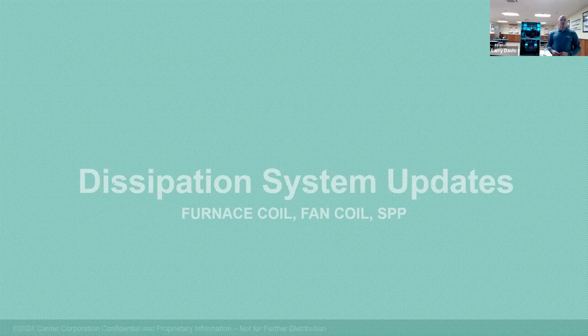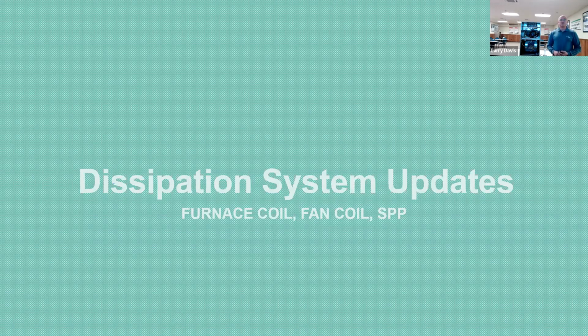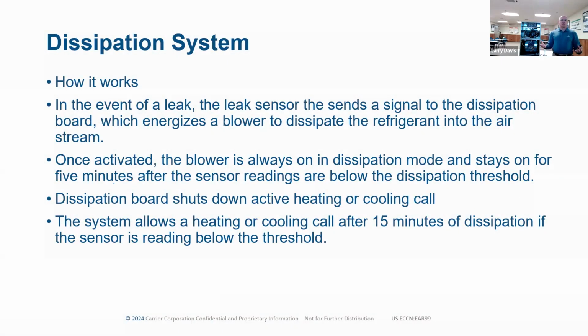All right, let's look some more at our dissipation system. So the way it works, we have a leak sensor. We have a sensor in there, and it's tied to a mitigation board, or a dissipation board. When it senses a refrigerant level above the 20%, it's going to go into a dissipation mode. It's going to stay on for at least 5 minutes. When it's in dissipation, there's a little light on there that'll tell you that. It shuts off our heating and cooling system and energizes our indoor blower. It's going to run that blower for a minimum of 5 minutes.